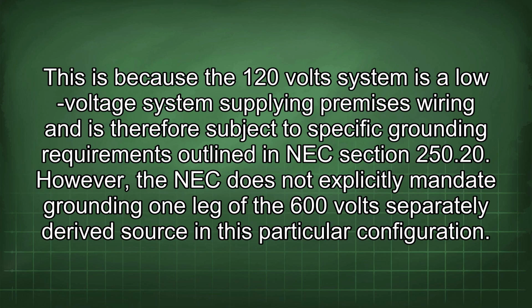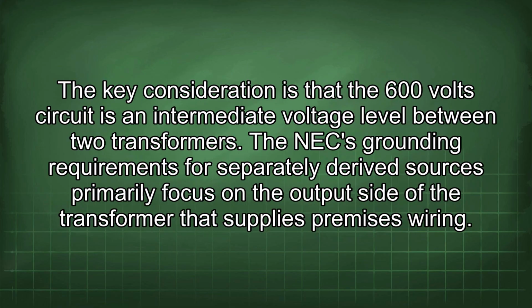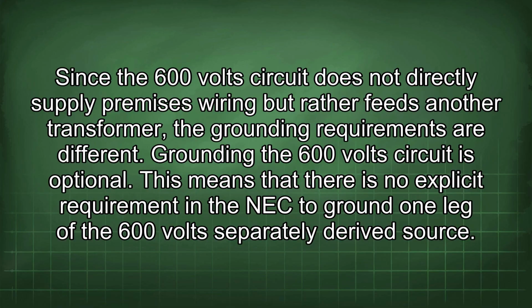However, the NEC does not explicitly mandate grounding one leg of the 600 volt separately derived source in this particular configuration. The key consideration is that the 600 volt circuit is an intermediate voltage level between two transformers. The NEC grounding requirements for separately derived sources primarily focus on the output side of the transformer that supplies premises wiring. Since the 600 volt circuit does not directly supply premises wiring, but rather feeds another transformer, the grounding requirements are different. Grounding the 600 volt circuit is optional.